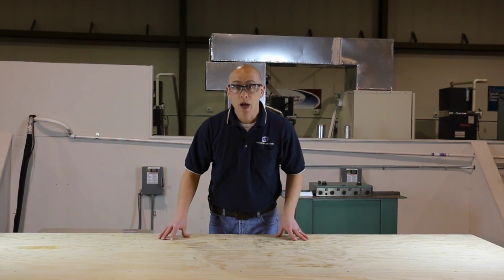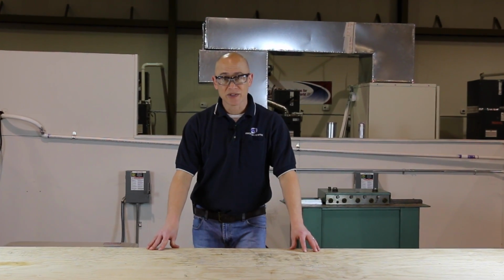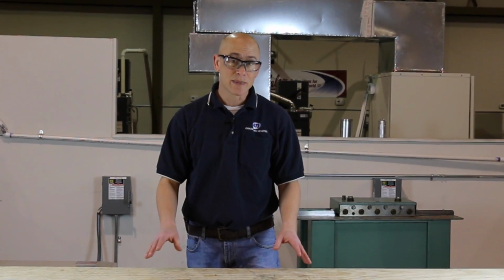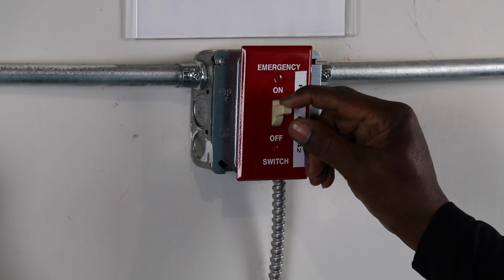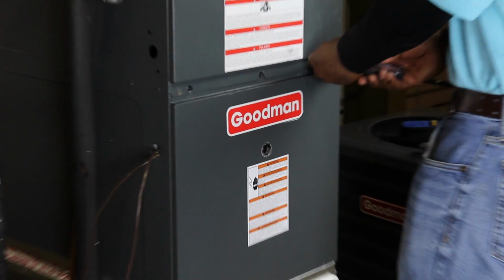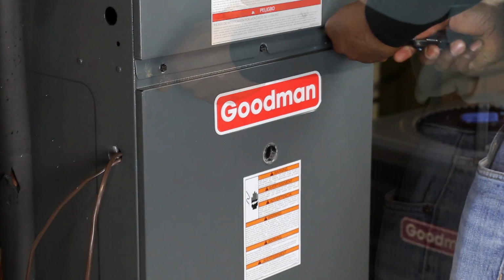Working on a bench is great, but most of the time out in the field we're not going to have a bench available to us. So we're going to have Darren demonstrate these troubleshooting techniques on an actual furnace. Darren starts by killing power at the switch. If this were a 240 circuit, it would be the disconnect.